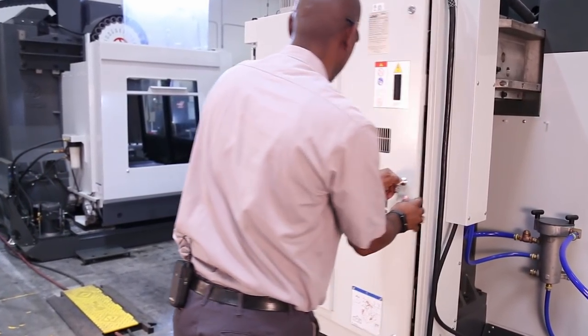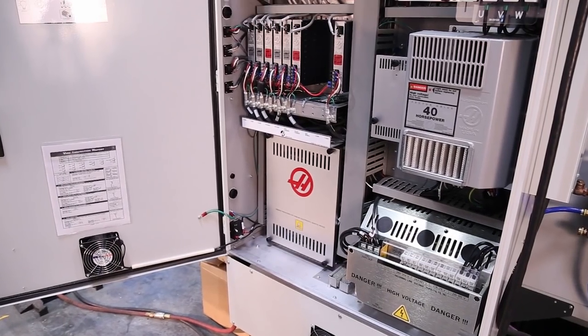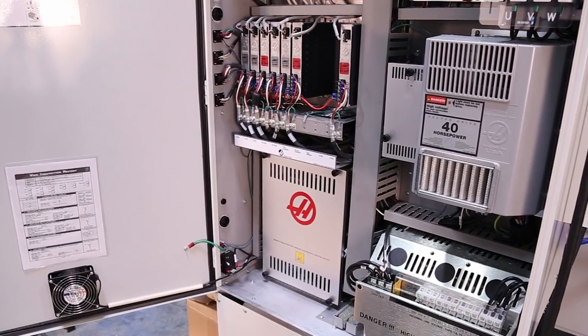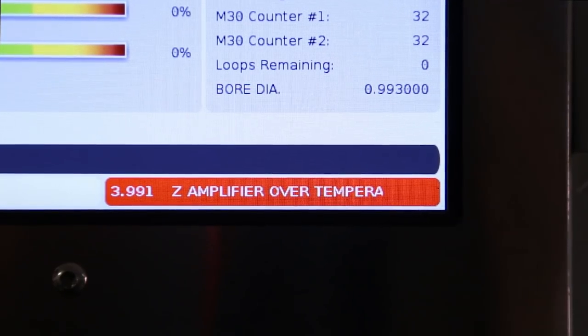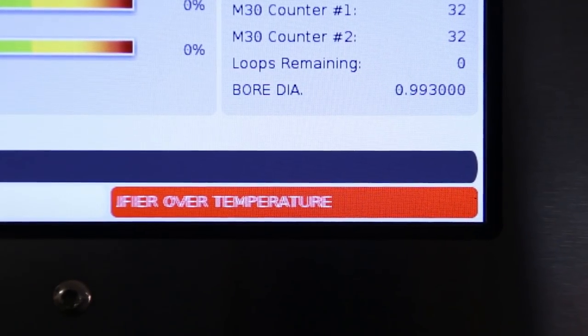Each axis in the machine has a servo amplifier that powers the servo motors. If the servo motors draw an unusually high amount of current from the amplifiers, the amplifiers can heat up and trigger an amplifier over temperature alarm.